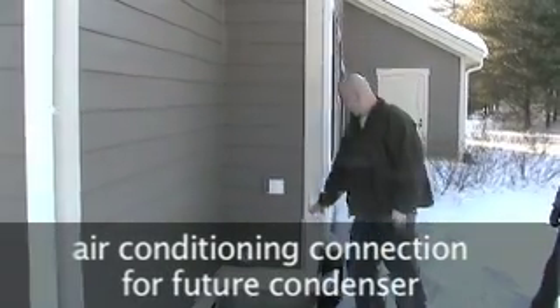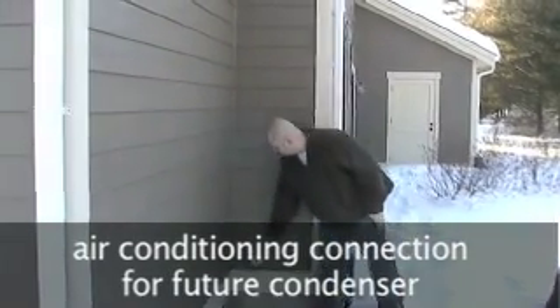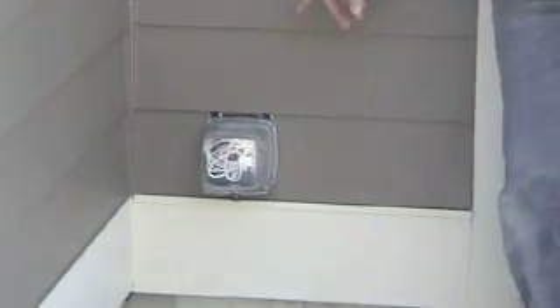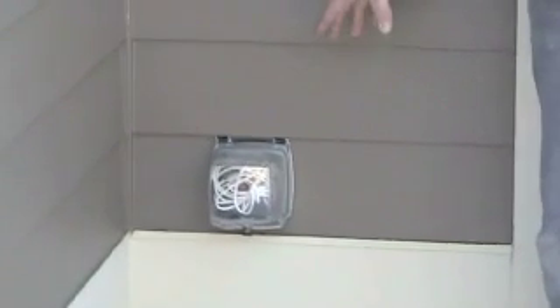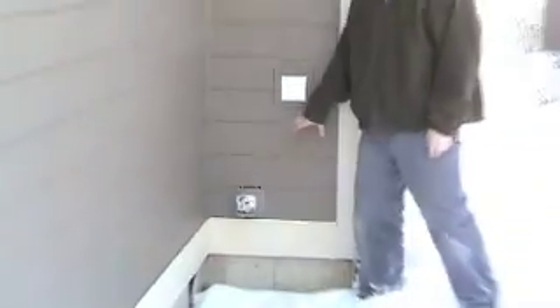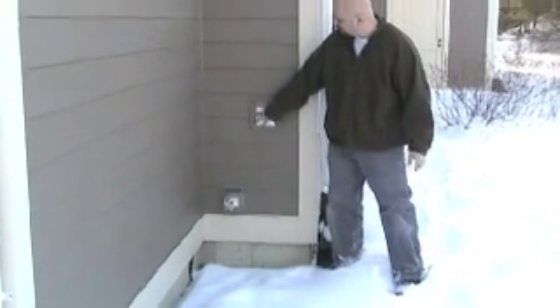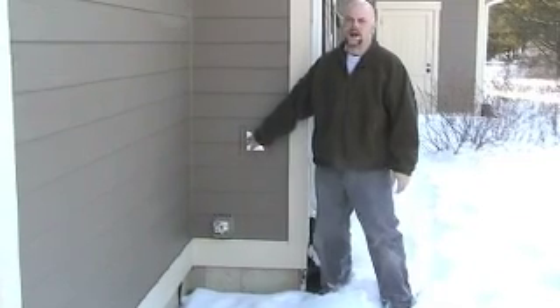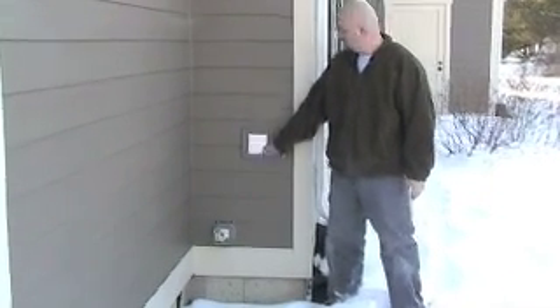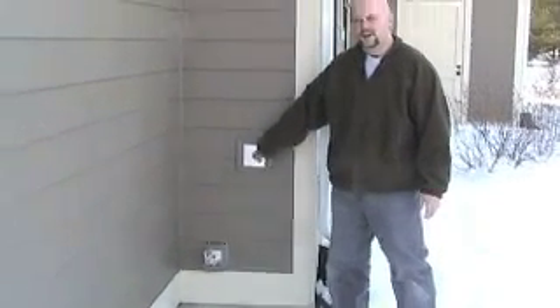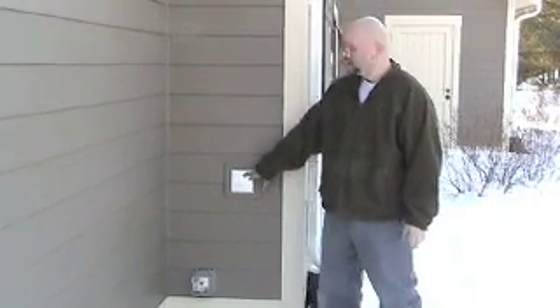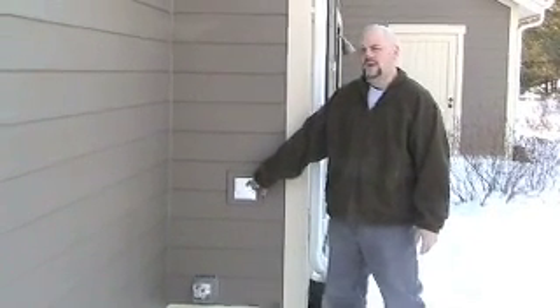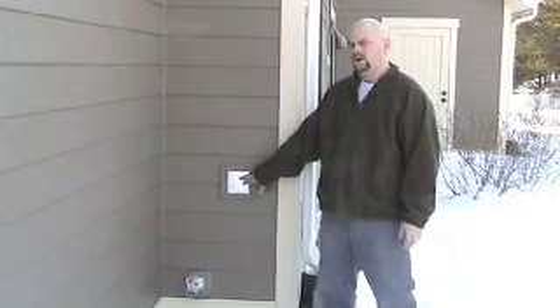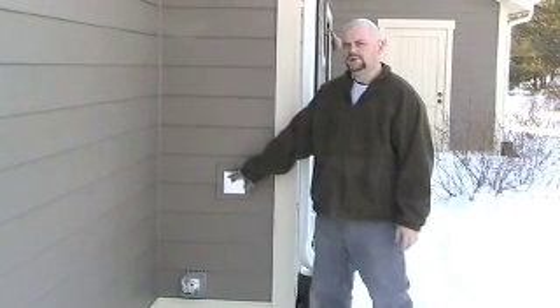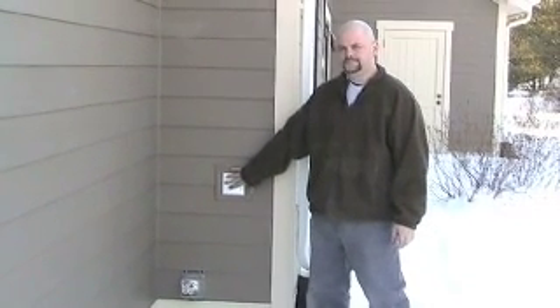On the back side of every unit, there is a connection for a future condenser for air conditioning. There's the line set and the T-stat wire underneath this in-use cover, and here is the location for the future power of the condenser. There is a box behind here and a run of ENT with a pull string back to the electrical panel for future pulling of wires to here for the condenser.